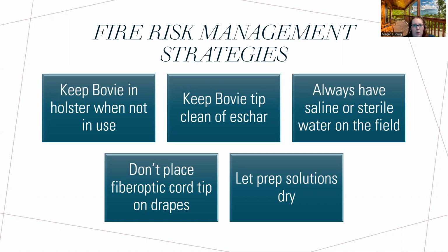Never throw that holster away. It needs to be attached to the drapes in an easy to reach position that allows the surgeon to get that out of there pretty easily. What can happen is if you leave the bovie out of the holster and on the drape, sometimes surgeons are trying to move around to see, they might inadvertently put their arm on the bovie and activate those buttons and burn a hole in the drape really quickly. I've seen it happen. So that's on you.